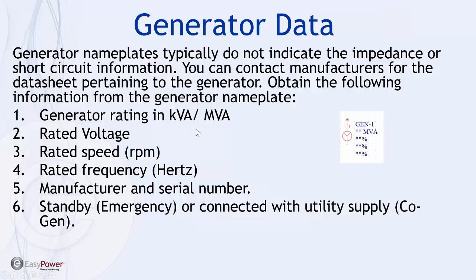Generators also have an important part — even though we may only have operations on a generator for a short period of time, or sometimes an unexpectedly long period, they need to be included in the arc flash assessment. In some cases they can be the restricting scenario if there needs to be inspection or maintenance while under generator power. The generator rating in KVA or MVA, the rated voltage, rated speed, frequency of the power generated, manufacturer and serial number are all critical. Frequently you'll have to get sub-transient reactance data off the data sheet, and the tools can help identify this through the EasyPower data dialog box for generators.